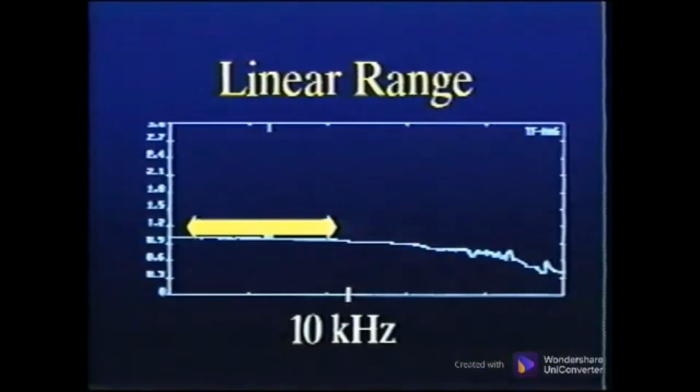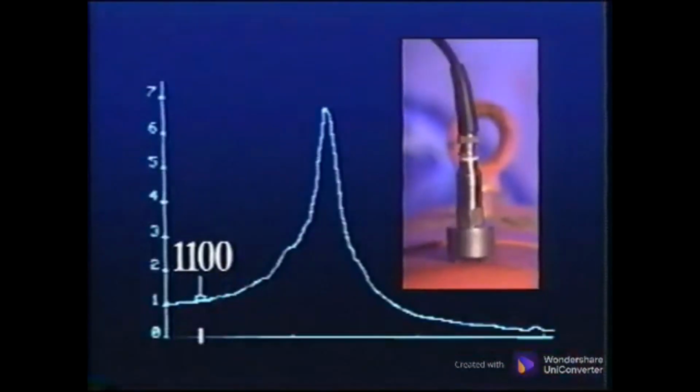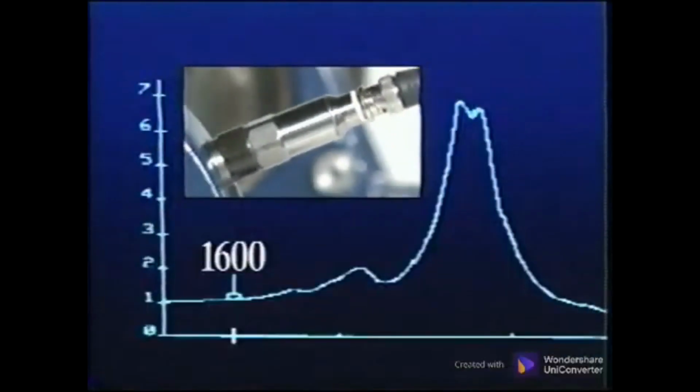Even when the analyzer can process frequencies this high, the first gear mesh frequency of this compressor is well above the linear frequency range of most transducers. A special transducer will be required, which is linear in these frequency ranges. Collecting data for these high frequencies requires special mounting techniques. Most magnet mountings provide linearity to only about 2,000 Hz.